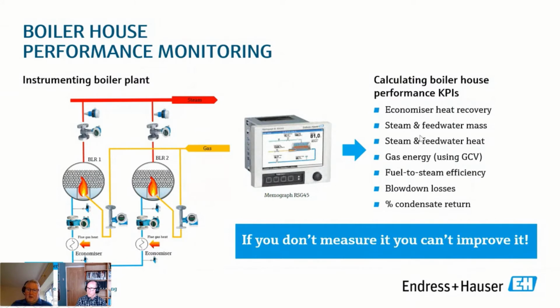We're going to look at what we can do with the information from those instruments - looking at the economiser heat recovery, comparing that across more than one boiler, which can act as a condition monitor and give us information on how that boiler's performing. We need to obtain mass before we can get to energy, so although you see lots of volumetric meters on boilers, without getting to mass first we can't get to energy - we'll look at what we need to do there.